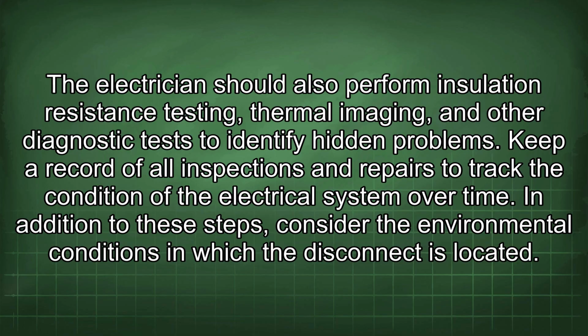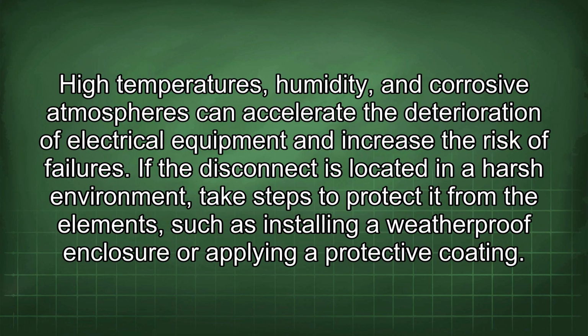In addition to these steps, consider the environmental conditions in which the disconnect is located. High temperatures, humidity, and corrosive atmospheres can accelerate the deterioration of electrical equipment and increase the risk of failures. If the disconnect is located in a harsh environment, take steps to protect it from the elements, such as installing a weatherproof enclosure or applying a protective coating.